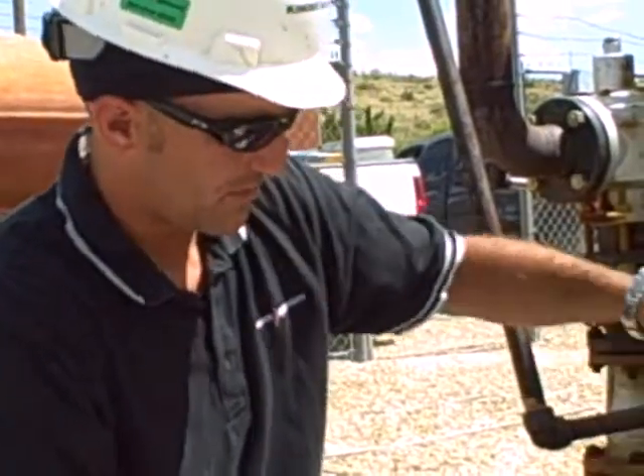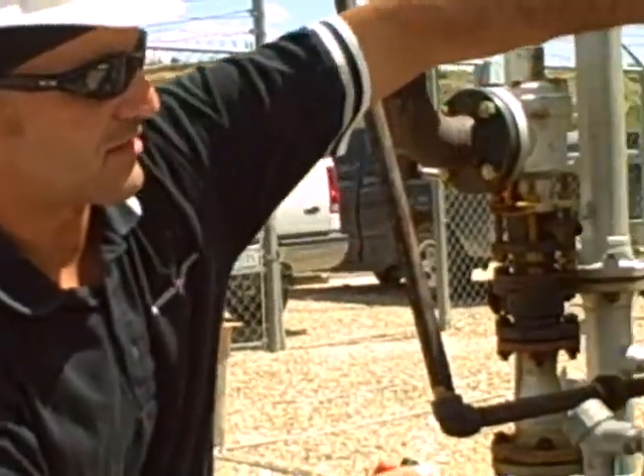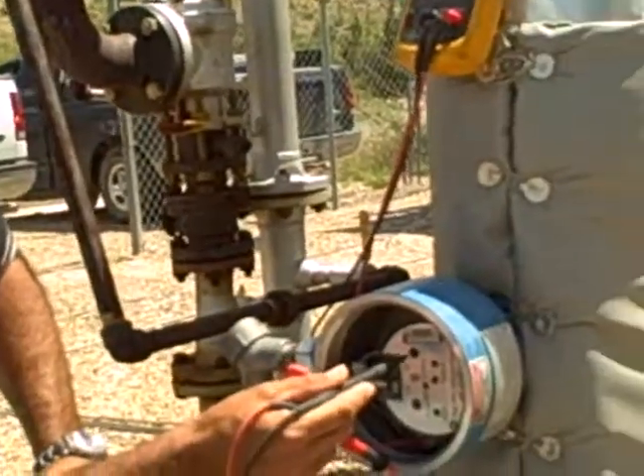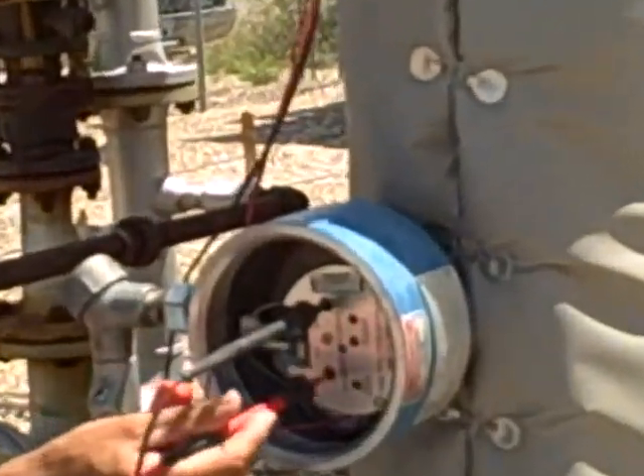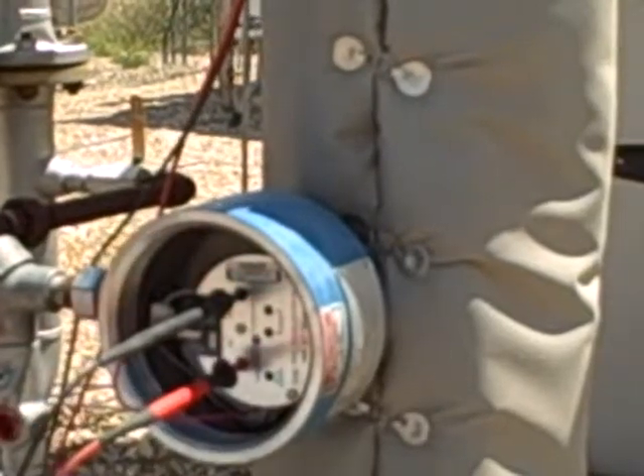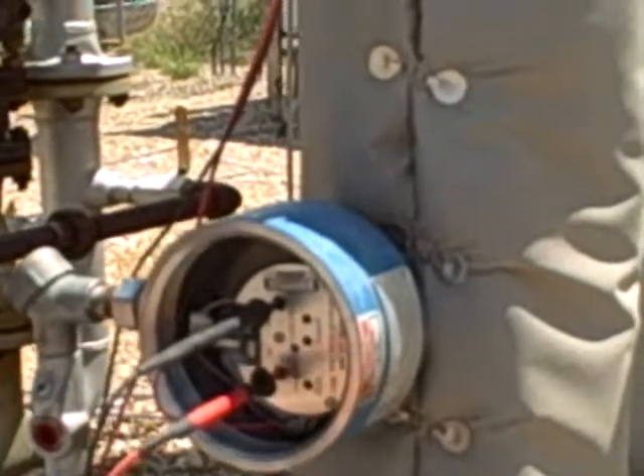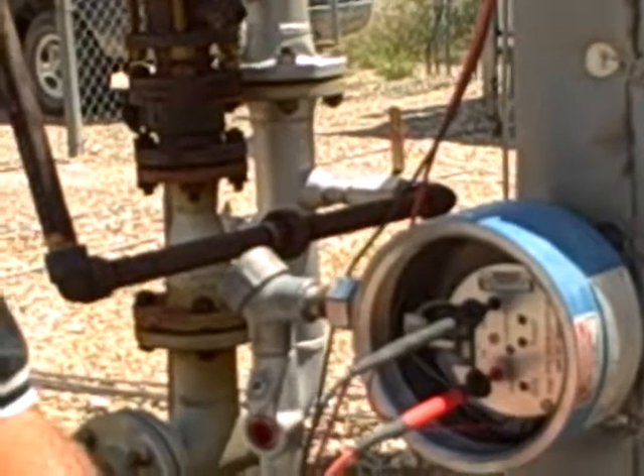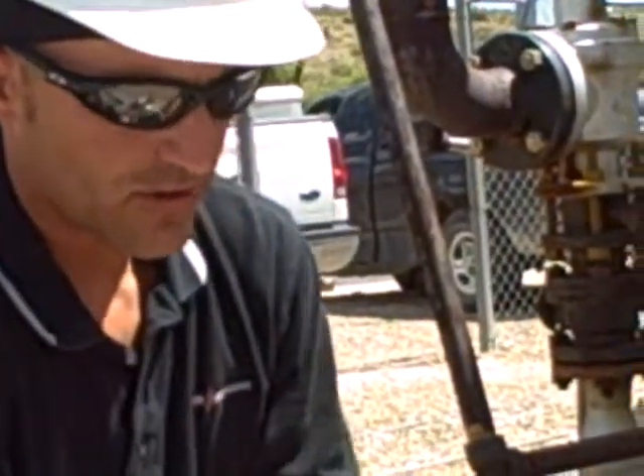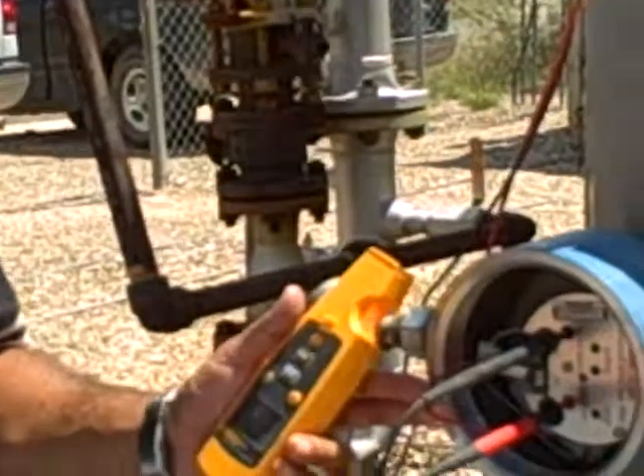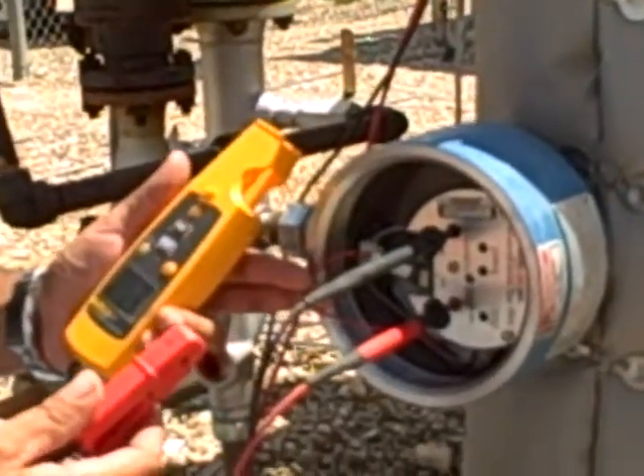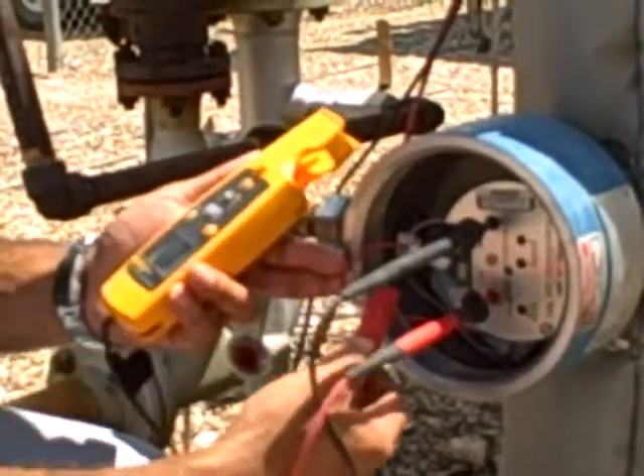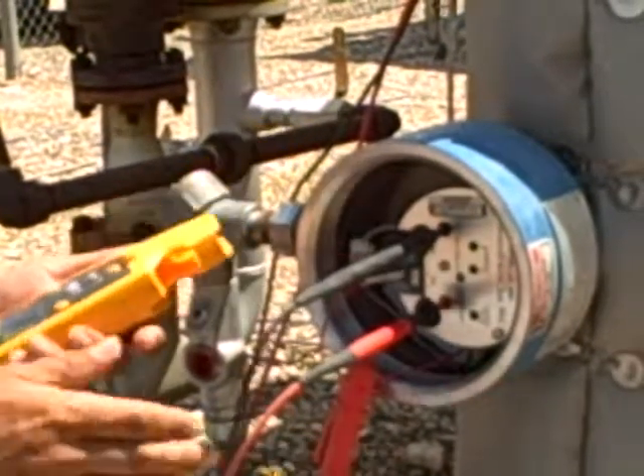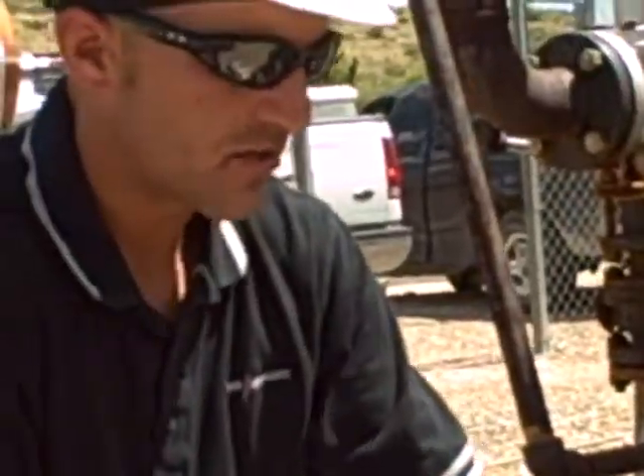So I'm going to go ahead and turn my Fluke on. I set it to voltage DC. Hook it in here on the calibration ports. One's black, one's red. It corresponds with your leads on your Fluke. I'm going to go ahead and turn on my Fluke 771. Okay, it's powering up, and I make sure it's zeroed. Now on the 771, when you hook it up on this red wire here, which is the 4 to 20 milliamps, I'm going to hook it up with the arrow facing away from the card. Alright, I got it hooked up now.